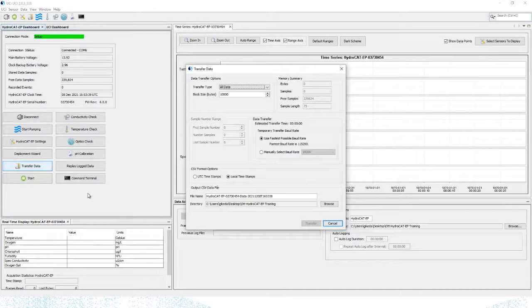I don't think I actually have any data on this instrument yet, 0 samples. If I had some data on this instrument, it would tell you how much is there, and then you can transfer either all the data from the instrument into a single CSV file, or you can pick a range of sample numbers. Say you just want to look at the last week and a half of data just to make sure that your instrument is outputting something, is measuring reasonably correct. You can set it to say it has 5,000 samples. I know that encompasses a month. I might want to do sample 4,000. It's just not going to let me do that because there's not 4,000 samples. Say sample 5,000, just to get the last bit to take a look at it. Totally up to you. I like to just upload all the data on the memory.